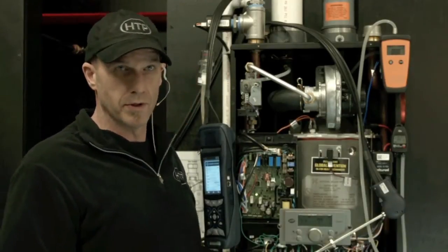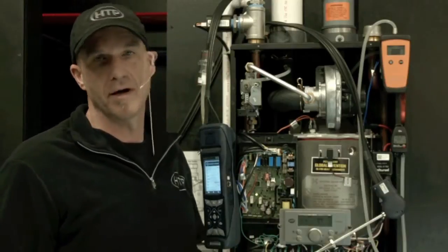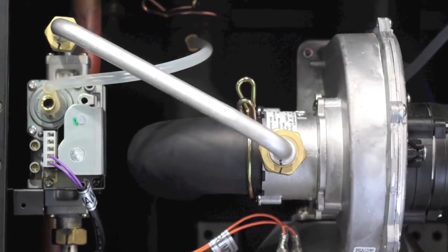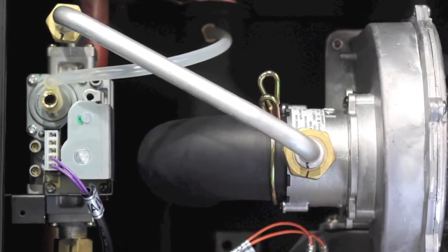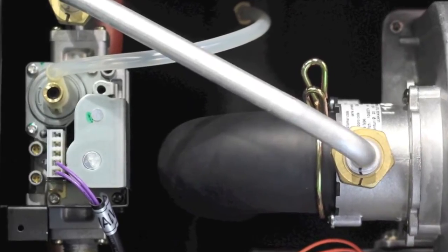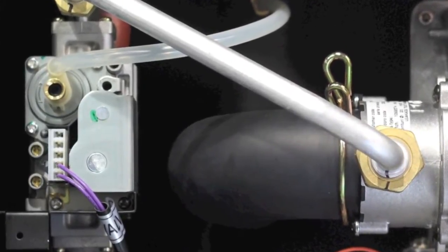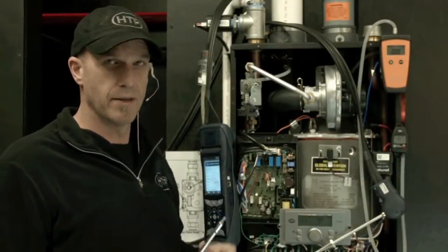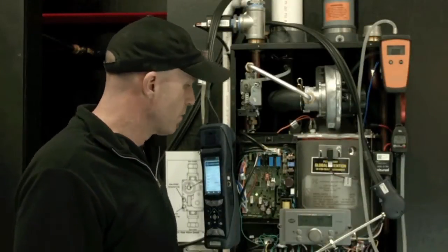And we are also going to look at low fire combustion and high fire combustion. So this is a single orifice gas valve. We use a throttle screw on some particular valves. This one only has a manifold pressure adjustment or an offset adjustment. We use an orifice to do our maximum, so there's no need to adjust a variable orifice within the valve. So again, they're single orifice valves.